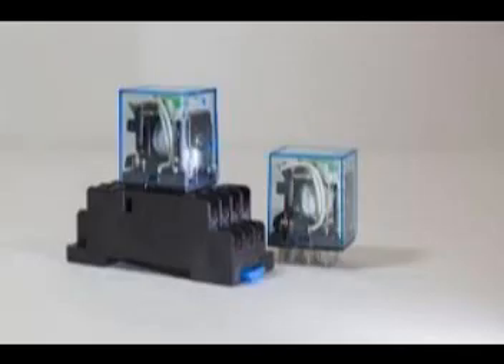So normally open means the path is broken until you power the relay. Makes sense. What about normally closed, or NC contacts then? Normally closed or break contacts are just the opposite. When the relay is off, coil de-energized, these contacts are already closed. Current can flow. Then when you energize the coil and the relay switches, these NC contacts open, breaking the circuit. Got it. So it's all about that default setting, when the relay isn't actively doing anything.